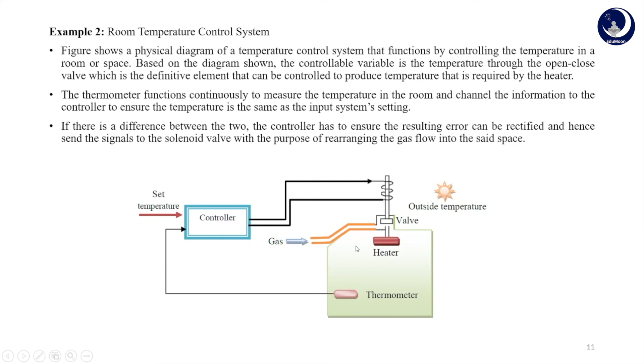This thermometer is the sensor attached to the actual control system that gives the feedback to the controller, and it constantly gives the temperature reading in the room and channels the information to the controller to ensure the temperature is the same as the input system setting. In this case or any case, the comparator, the part that compares the set temperature or the set point, is implemented in the controller. If there is a difference between the two, the controller has to ensure the resulting error can be rectified and hence send the signals to the solenoid valve, which is responsible for rearranging the gas flow into the set space.